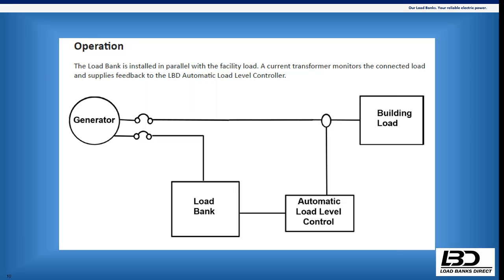In an event of a failure, I'm not sure exactly what's intended, or what we're classifying as a failure. Let me try to imagine what he's thinking. So, let's say you lose all control power to that load bank. Will the steps fail open or closed? I mean, they're contactors, right? So they're all going to open, right?